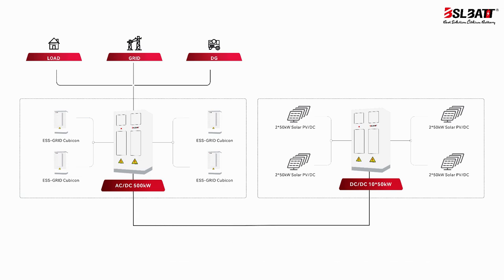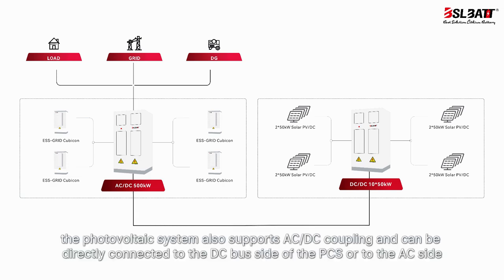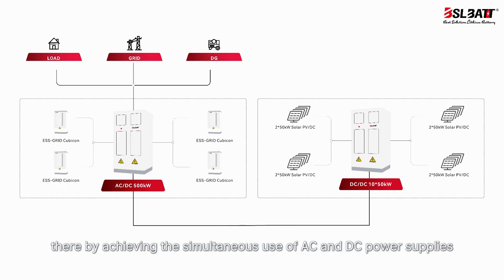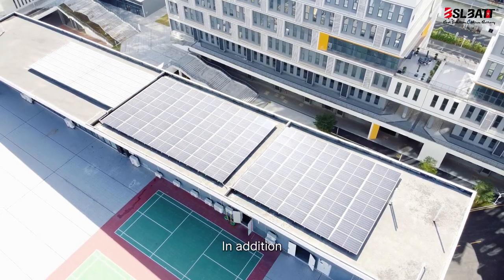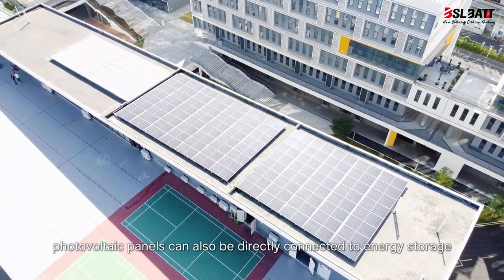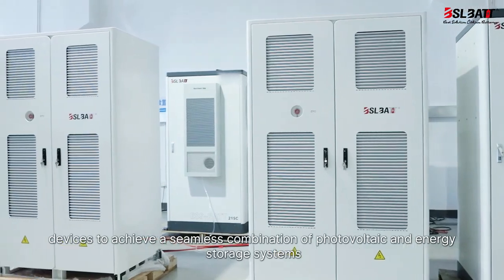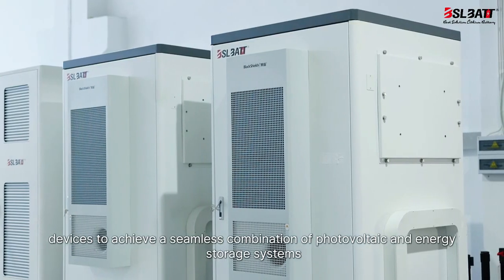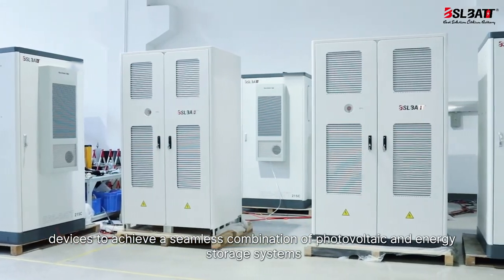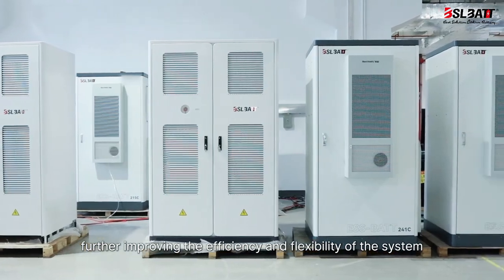At the same time, the photovoltaic system also supports AC-DC coupling and can be directly connected to the DC bus side of the PCS or to the AC side, thereby achieving the simultaneous use of AC and DC power supplies. In addition, photovoltaic panels can also be directly connected to energy storage devices to achieve a seamless combination of photovoltaic and energy storage systems, further improving the efficiency and flexibility of the system.